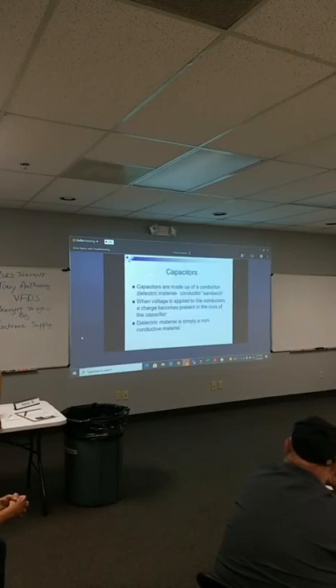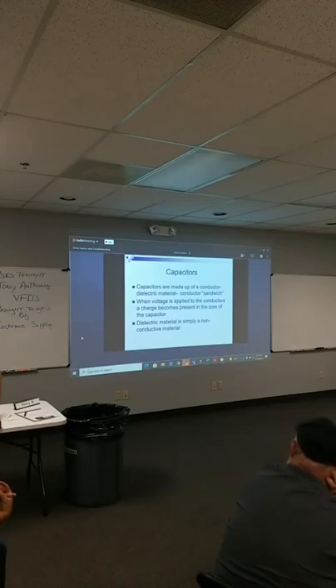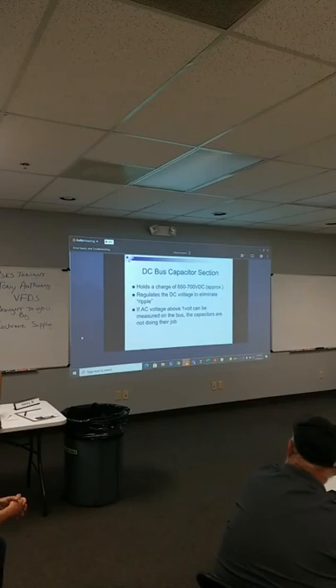Capacitors are made up of dielectric material. I'm going to skip through some of this because it's not the kind of stuff I even remember. DC bus, here we go. This is for a 460 system. Charge of 650 to 750 or 700. On a 240 system, like I said, it's going to be somewhere around 350.